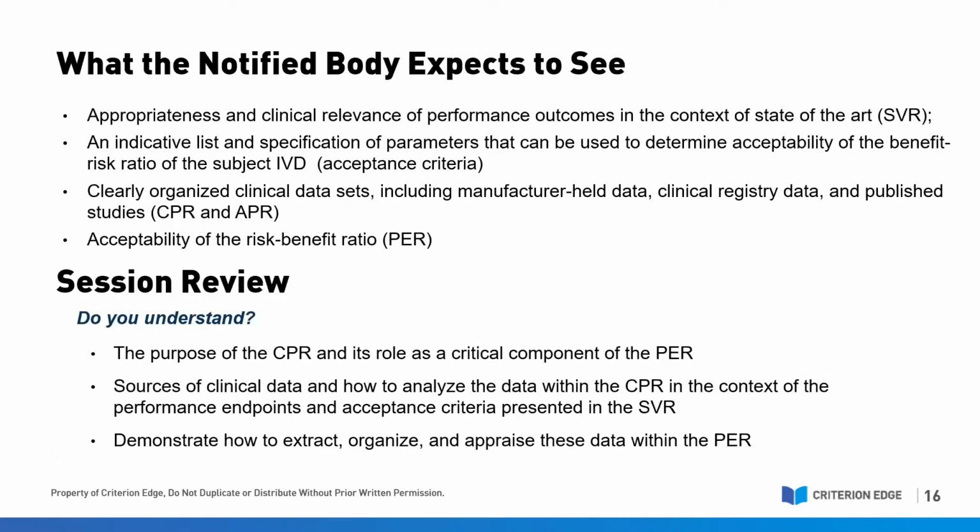So in conclusion, we'd like to remind you of what the notified body expects to see in the process of presenting your data within the CPR. They expect that you will have identified meaningful performance endpoints, but also support the appropriateness and the clinical relevance of these performance endpoints in the context of what can be considered state of the art. They want to see an indicative list and specification of the parameters that you use to establish your acceptance criteria. And then finally, they expect to see actual analytical data and clinical data pertaining to your IVD, and that will be used to determine the acceptability of the benefit-risk ratio for the subject IVD.